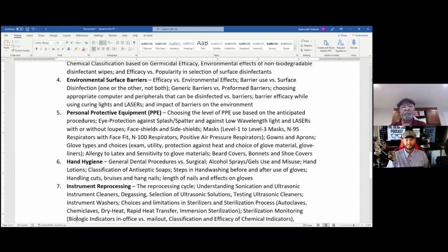Against buying good stuff. Now, the sterilization milk, that has been taken care of for most purposes. If you still want to, you can still get it, but you use it after you clean your instruments, pat dry them, apply a drop at the hinged areas, and then bag it and stick it in. You're fine. So that is one. Then when you load your instruments, don't overload your instruments. That sterilizer is not going to run away.